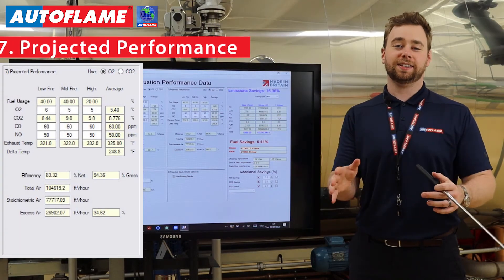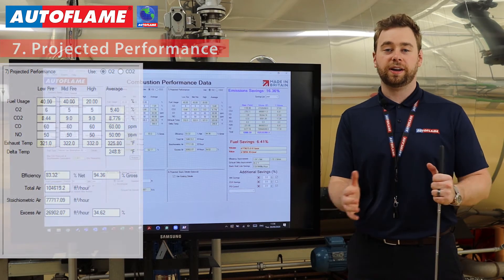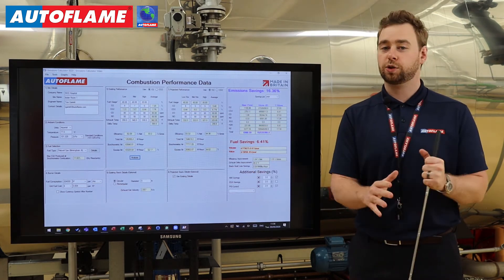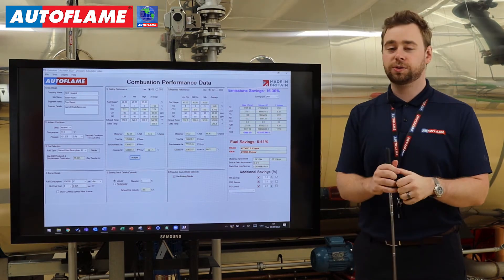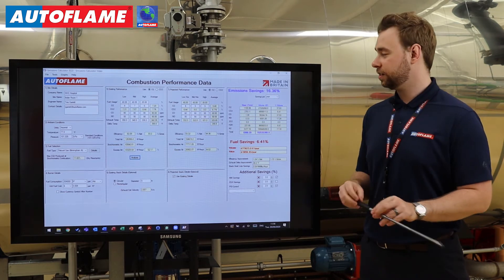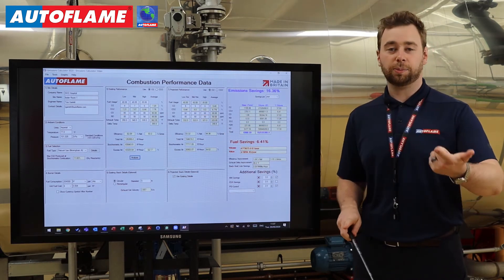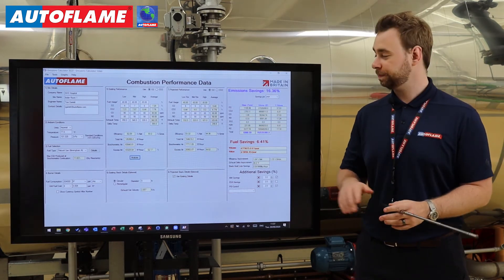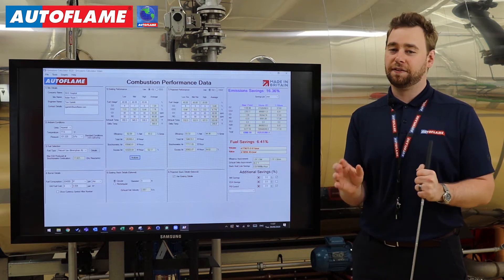Section seven is your projected performance data. This is really dependent on whether you're installing a brand new burner or just retrofitting and upgrading that control system. Dek's been on site and given me the existing data. We know we're going for a controls upgrade in this case, so we're going to use historical performance data to input O2, CO, and NO values at high, mid, and low fire positions. Based on this particular burner type, size, and various factors, I know for low fire I'm putting in 6% O2, and for mid and high fire 5% O2. The CO across the board is dropping to around 60 ppm, and we're keeping the NO the same at 50 ppm.